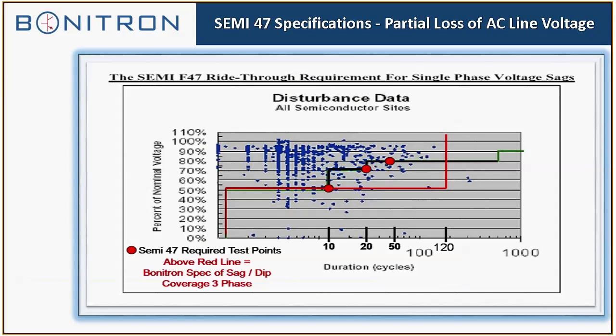This just shows what third-party testing looks for when they're testing ride-through. They look at sag depth and they look at time. And this shows the SEMI F47 test, and we actually go above and beyond SEMI F47. The requirement is only 200 milliseconds, but Bonitron sag ride-through will cover the red line, which is 50%, for 2 seconds. You look at the red dots, those are the test points that the third-party organization tests for to be able to say you're certified to handle the SEMI F47 spec.